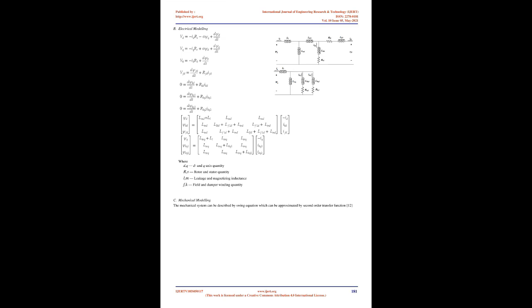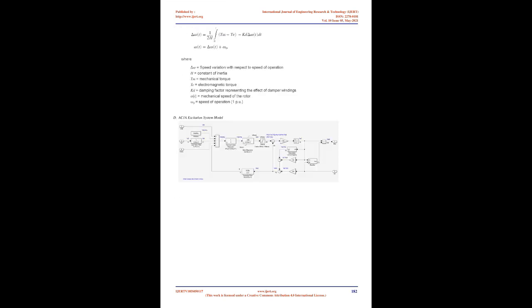The second event occurred at time t equals 50 seconds when an extra load of 300 kW was added suddenly, which caused another disturbance to the grid. As the load increased, the frequency of the machine slowed down to 59.9 Hz, and then sped up to 60.03 Hz until it settled back to 60 Hz within 5.6 seconds.